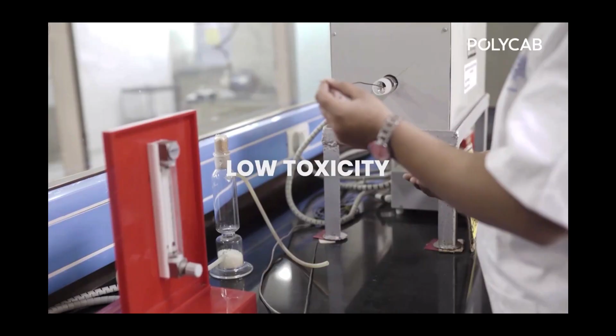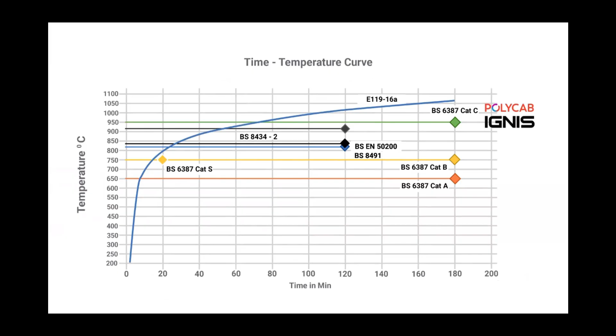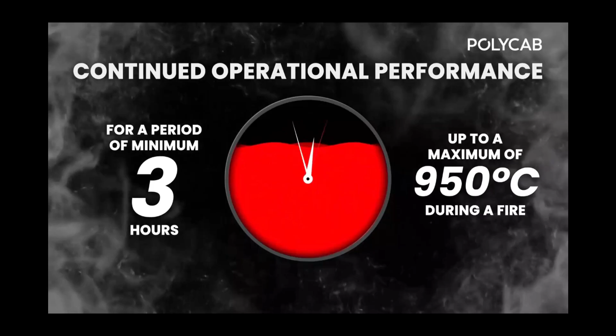The Polycab Ignis lowers the smoke opacity and gas emissions, prevents flame from spreading, and reduces heat release, making it a low fire hazard. By doing this, it reduces the possibility of deaths due to suffocation. Polycab Ignis complies with various specifications described under the time temperature curve for the standard fire endurance tests, meeting the standards specified by BS and IEC. It can maintain the power circuit integrity and keep it running for a minimum of up to 3 hours at a maximum temperature of 950 degrees Celsius, making it highly fire resistant.